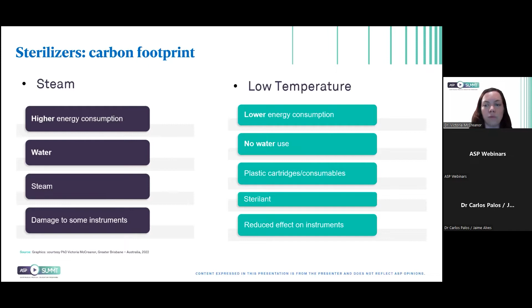The other important thing to think about is the carbon footprint of the consumables, the impact of the production, the impact of the waste from disposable products that might be used for indicators and testing, and also the choice of wraps and pouches, and trays that the devices are put in to be sterilized, and whether those are reusable or disposable. The other thing to take into account is the chemical production and disposal, for example, of the sterilant cartridges. I won't go into a lot of detail about what the carbon footprint is of those, because that's not my area of expertise, but they are definitely things that need to be considered, and may be context specific as well.